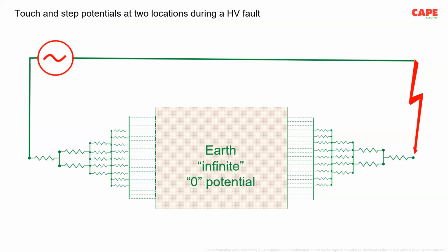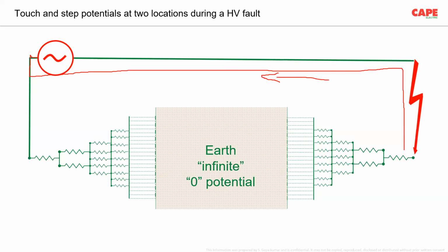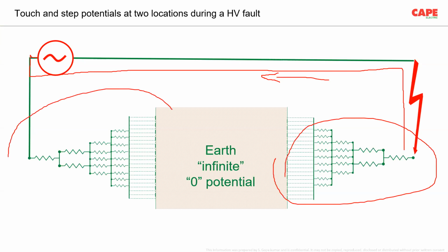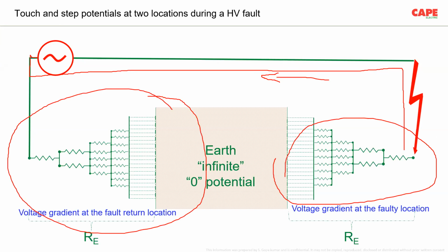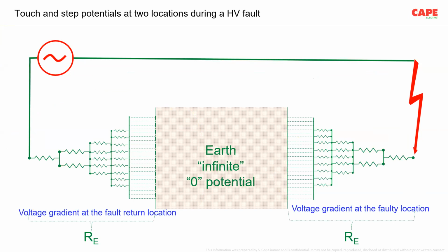Now, what you should always understand is, I am taking a red color line as the metallic fault return path. If there is a metallic fault return path, the majority of the fault current will flow through it. But for high voltage substations, where the distance between the source and the secondary switching stations is far away, maybe tens of kilometers, hundreds of kilometers, the fault return through the metallic conductor is probably less, and in some cases the low resistance of these earth electrodes is practical. So basically what you should understand is voltage gradients are created at the place of the fault as well as when the current is returning back to the neutral of the system.